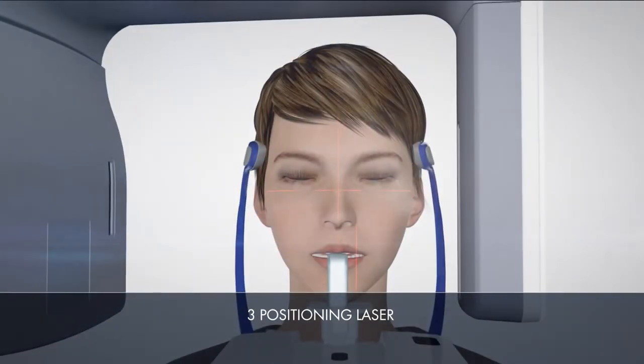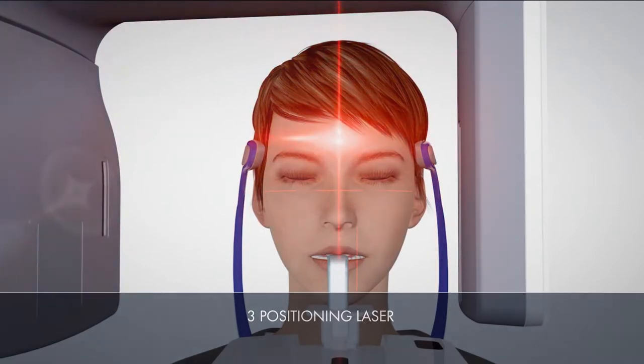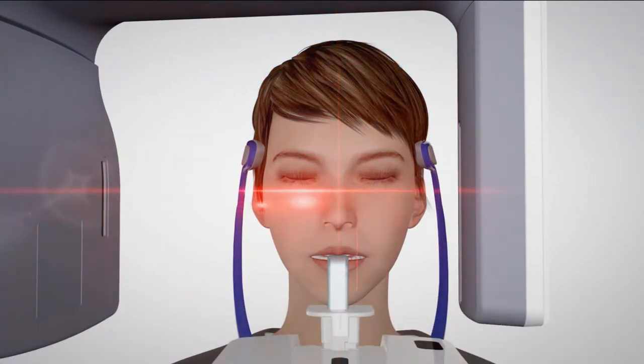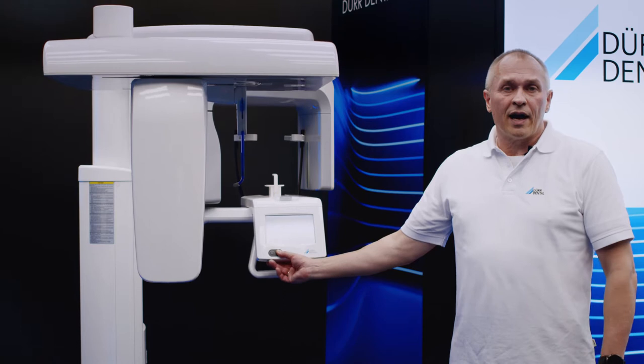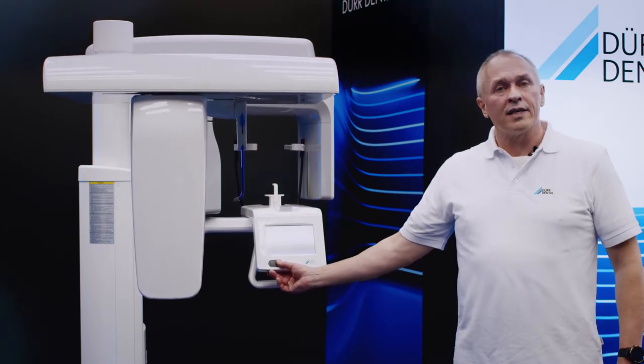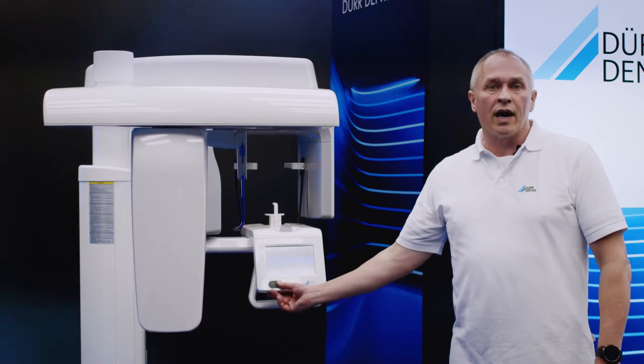Three positioning lasers help the operator to position the patient by precisely aligning the sagittal plane, the Frankfurt plane and the image layer plane. Generous vertical travel enables the Vista Pano S to be used with tall patients, children and even wheelchair users.